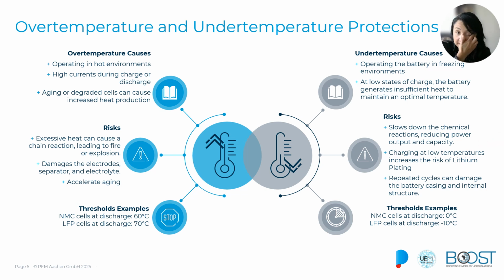And in this case, the BMS prevents all of these risks, again by restricting the charging and the discharging operation when the battery falls below those critical thresholds. For instance, in charging, usually the under temperature is going to be more critical than during discharging, and it will depend on the specifications of the system.